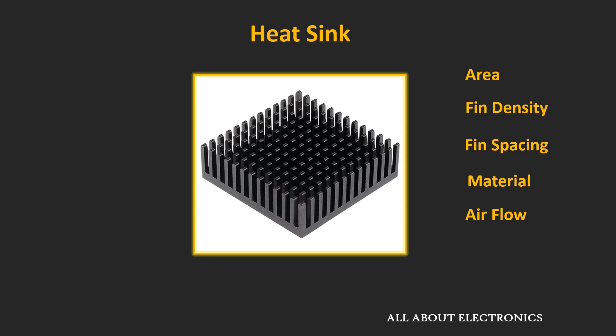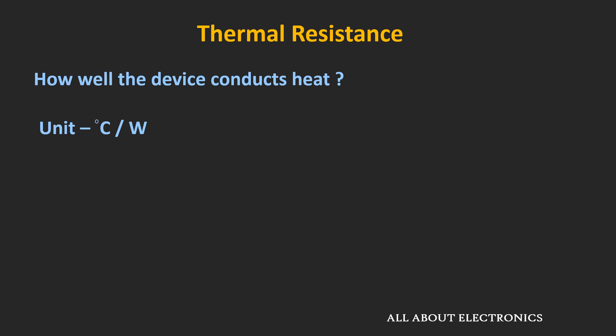For any heat sink, how well it transfers heat is defined using thermal resistance, which is measured in units of degrees centigrade per watt or degrees kelvin per watt. This tells us the rise in temperature of a device when 1 watt of power is applied. The thermal resistance of any heat sink should be as low as possible. For example, if a heat sink has a thermal resistance of 5°C per watt and absorbs 5 watts of power, the heat sink temperature will rise by 25°C. If the ambient temperature is 25°C, the heat sink will be at 50°C.